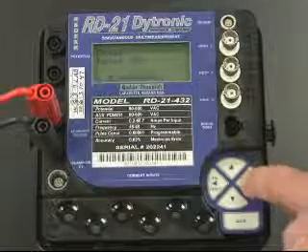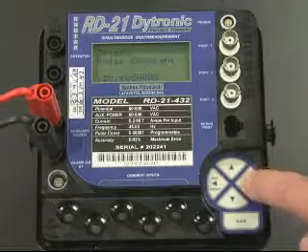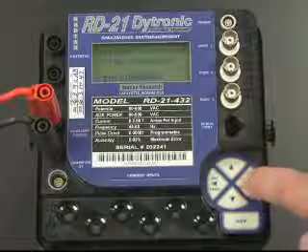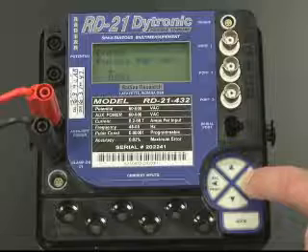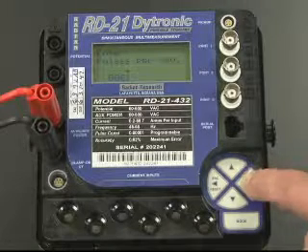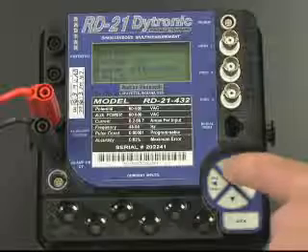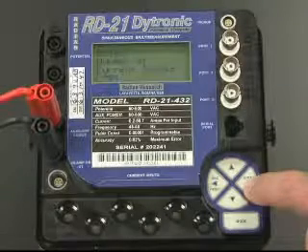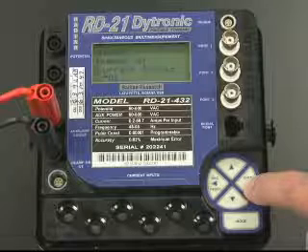Use the keypad to select the number of pulses per equivalent revolution on the meter and press the Enter button. Use the keypad to select the correct number of elements of the meter and press the Enter button. Use the keypad to select the correct number of current inputs being utilized, in this case select 1.